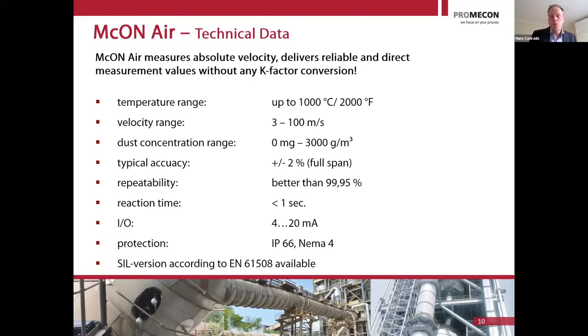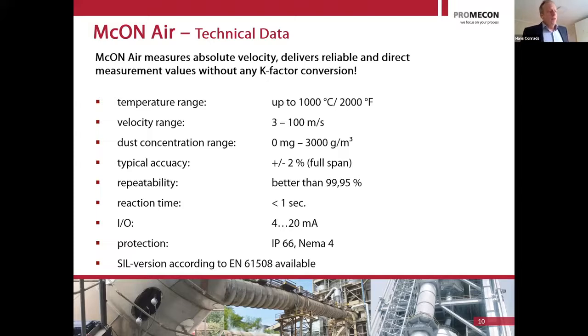We can measure from zero dust up to 3,000 grams per cubic meter — so we can measure the gas flow right out of a raw mill, including the main gas flow and the recirculation duct. Repeatability is our big strength: 99.95% or higher, because we are using a digital system. The digital clock repeatability is our repeatability — a digital clock is accurate to 10⁻⁵ or 10⁻⁶ — so repeatability is essentially a non-issue.